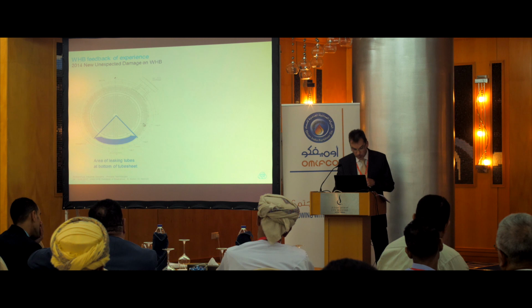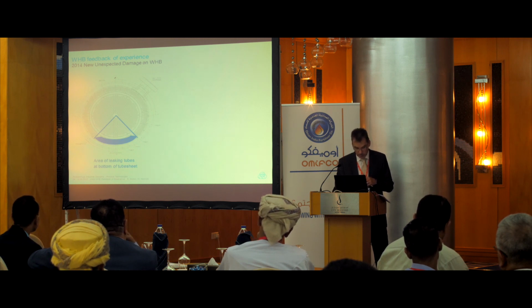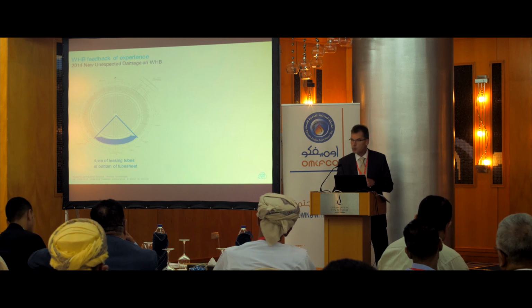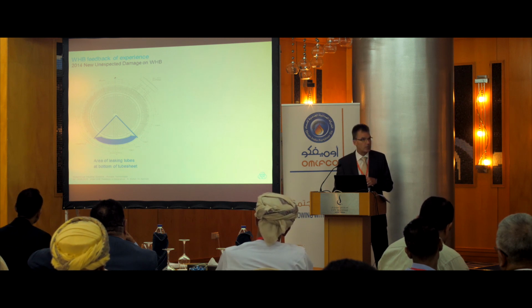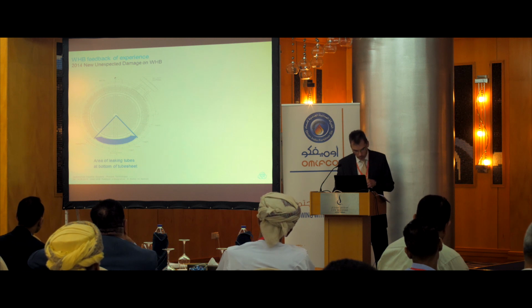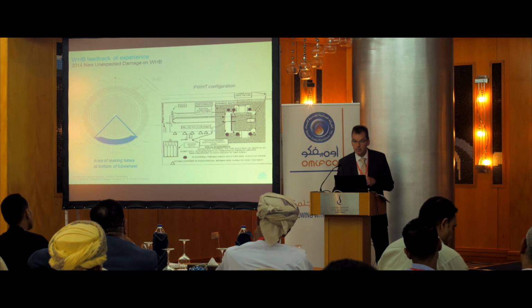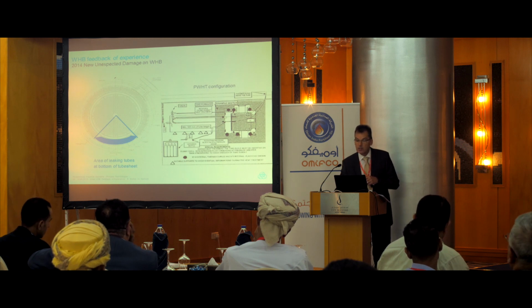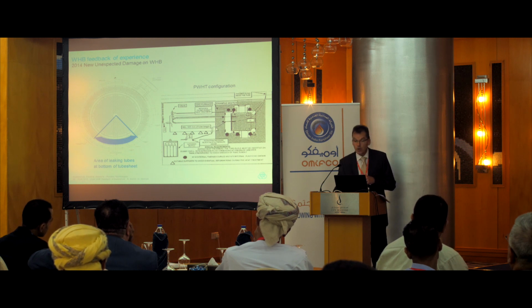Also, the leaks were not caused by tube wall thinning due to deposit corrosion. No, instead the leaks were a result of cracks within the tube-to-tube sheet welding seam. This was something new for us. During the root cause meetings at the manufacturer, we were informed that during the post-weld heat treatment, cracks had been experienced in the seal weld of the auxiliary shell. That means the shell is welded up here to the tube sheet and there had been a crack, and what did they do? Of course, they fed in nitrogen.